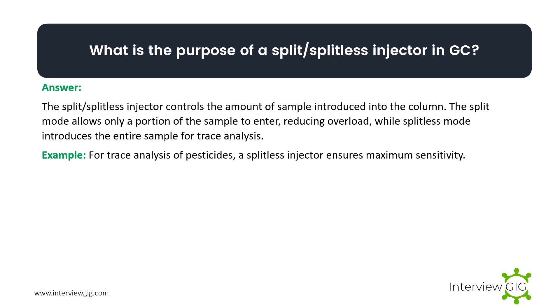What is the purpose of a split/splitless injector in GC? The split/splitless injector controls the amount of sample introduced into the column. Split mode allows only a portion of the sample to enter, reducing column overload, while splitless mode introduces the entire sample for trace analysis. Example: for trace analysis of pesticides, a splitless injector ensures maximum sensitivity.